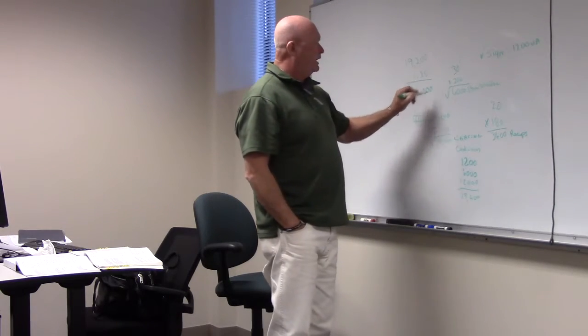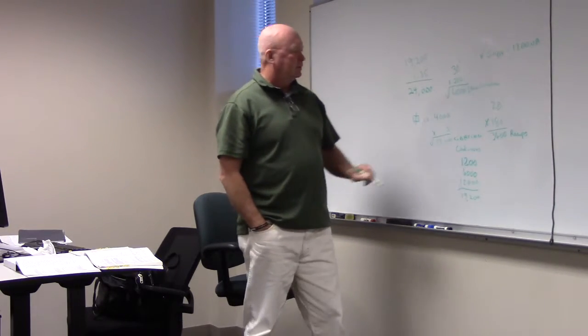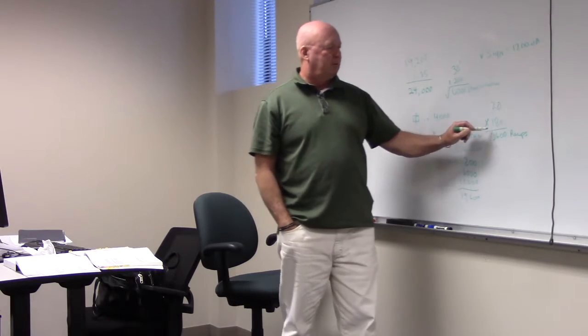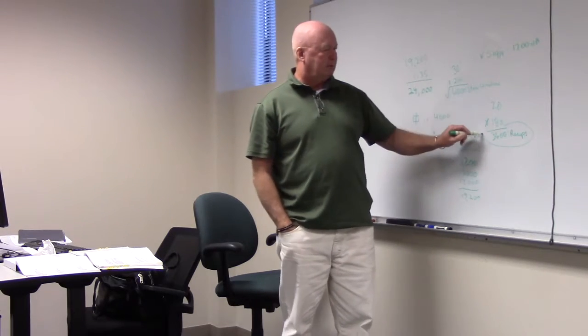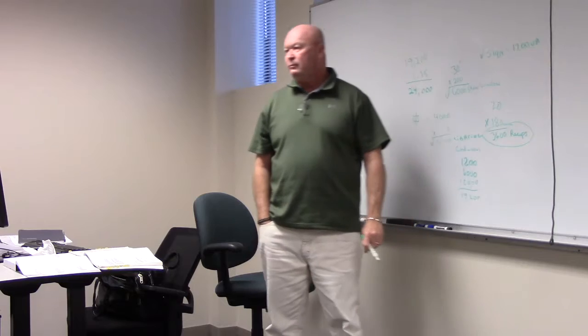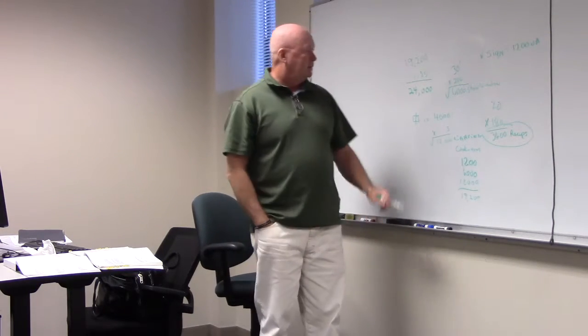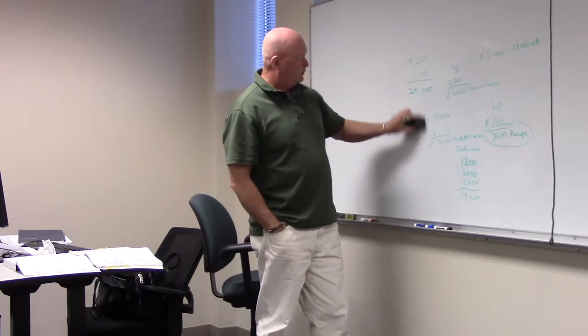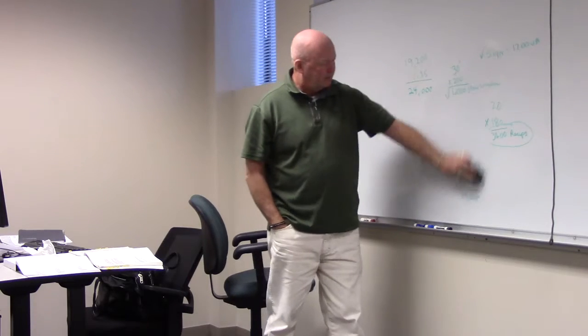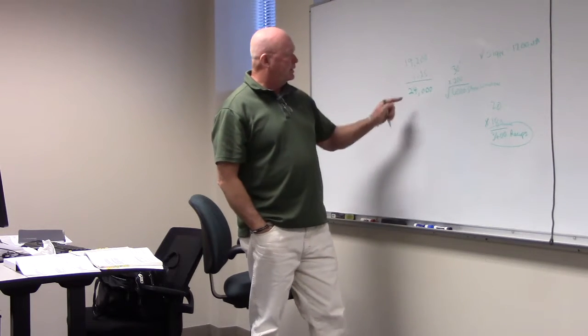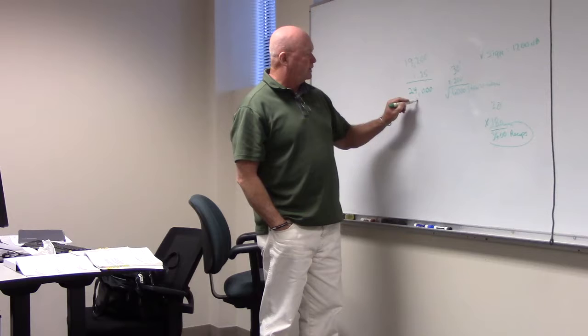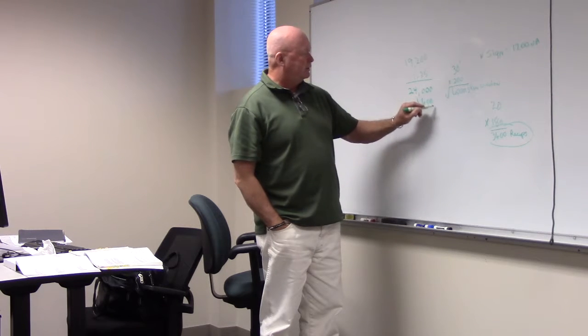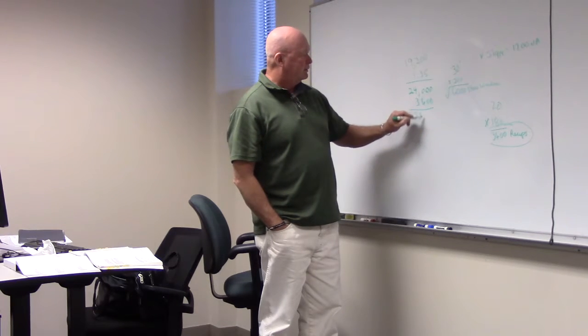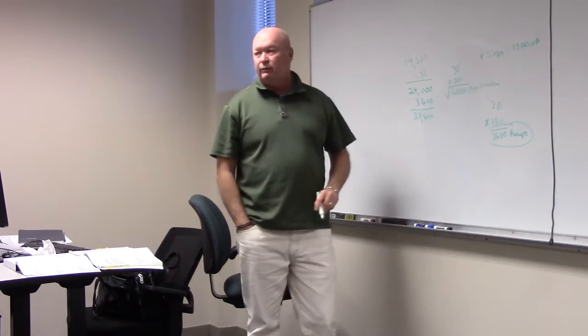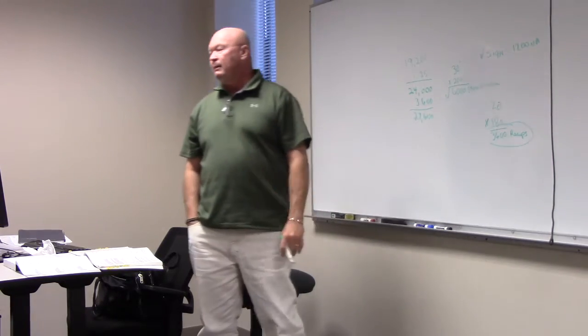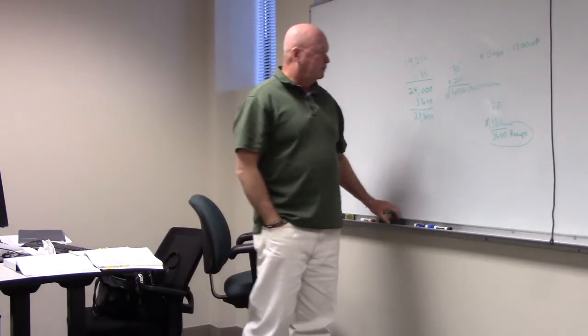Now, what do we still have left? What have we not done anything with? The receptacles. Exactly. So what do we have to do then? Add all these in. We're already down to here, so we're just going to add 24,000 to what? 3,600? Yes. 27,600. That's our total volt-amps for that building. Do you agree with me?